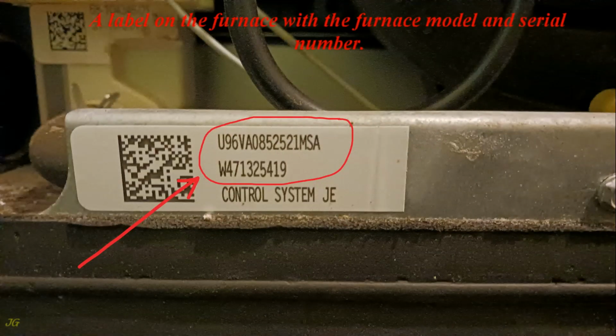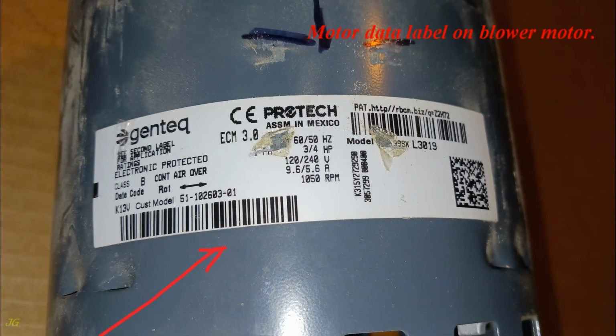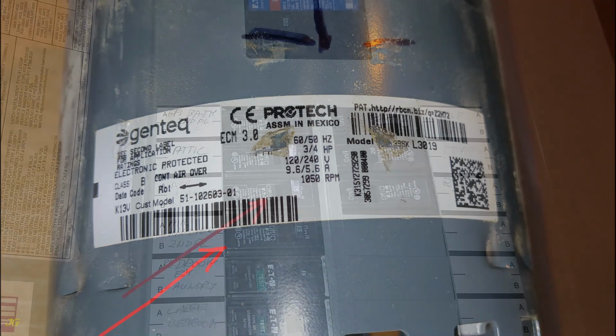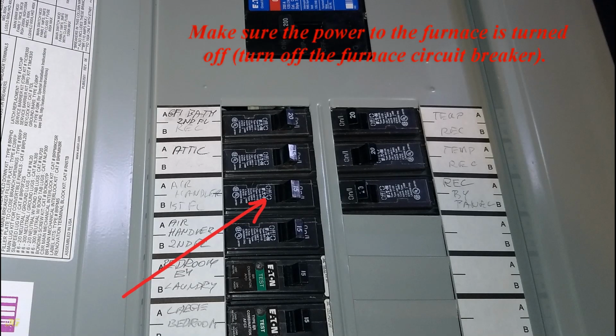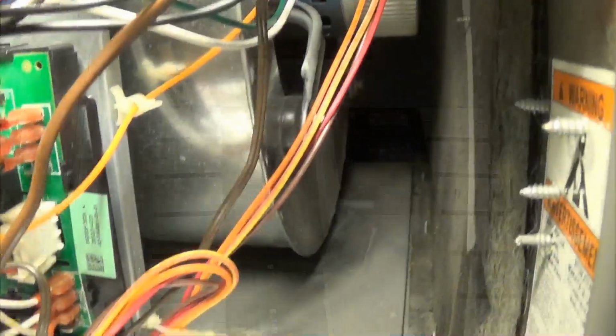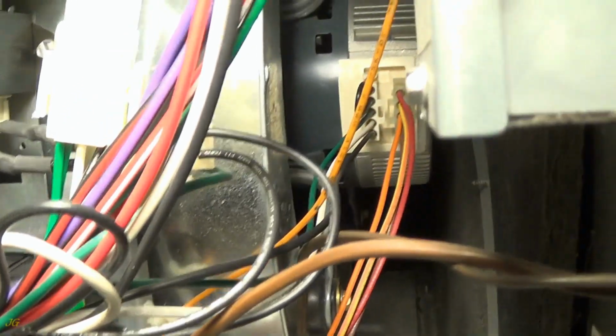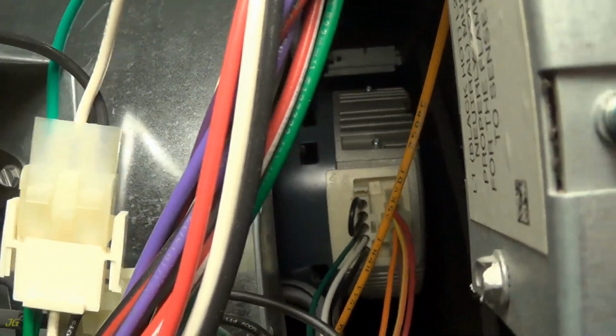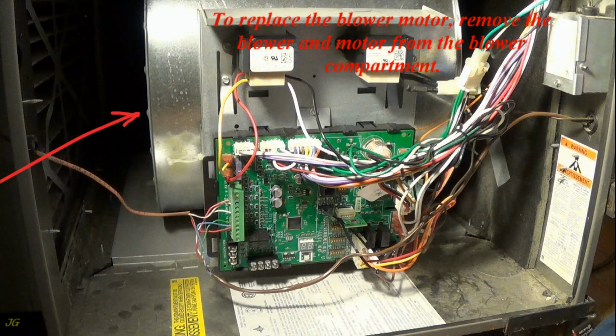A label on the furnace with the furnace model and serial number. Motor data label on blower motor. Make sure the power to the furnace is turned off. Turn off the furnace circuit breaker. To replace the blower motor, remove the blower and motor from the blower compartment.